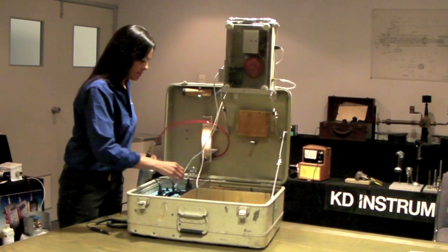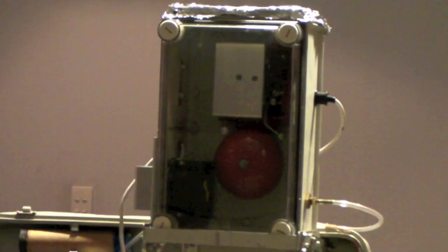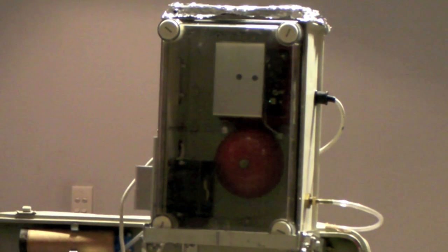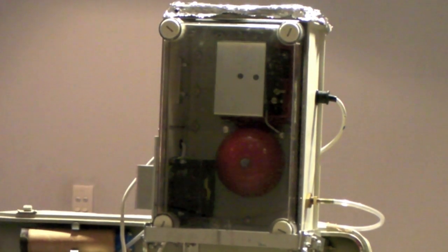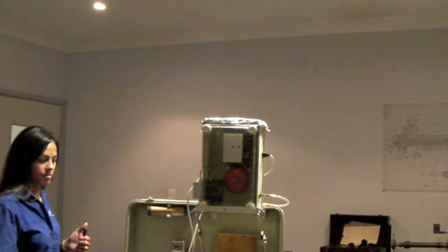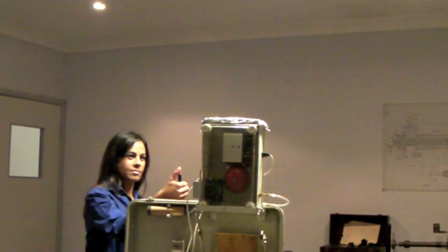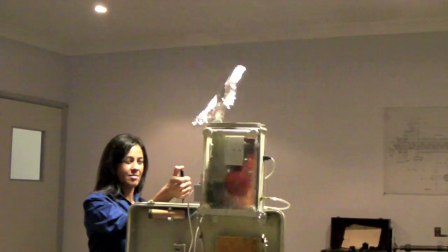A spark is an example of the third and final condition of our fire triangle, a source of ignition. However, our Bell circuit incorporates electronics which have been designed to limit the amount of energy in the spark and therefore will not let combustion occur in the hazardous atmosphere. As you could see, a small spark was generated, but still we had no combustion. Here's what happens when we remove the energy-limiting electronics from our Bell circuit.